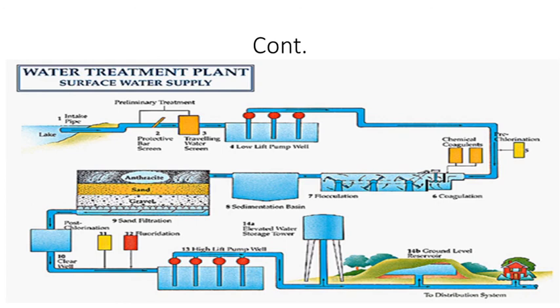The slow sand filter removes up to 99% of the bacterial load, and the rapid sand filter removes up to 80 to 90% of the bacterial load. If you consider turbidity, the slow sand filter can remove turbidity up to 50 ppm, that is 50 mg per liter. And the rapid sand filter removes turbidity up to 35 to 40 ppm.